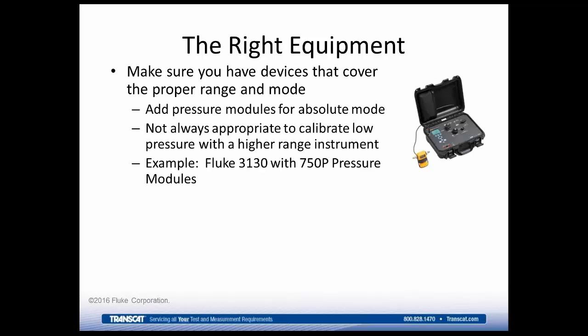And then finally, we need to make sure we have the right equipment. So make sure you have devices that cover the proper range and mode. If you've got a reference that's only a gauge mode device, but you routinely need to do absolute mode calibrations, then look at whether there are pressure modules or other such things, or maybe you need to get another device that can do absolute mode, so you can make sure that you're not inducing additional error that doesn't need to be there. It's also not always appropriate to calibrate low pressure with a higher range instrument. The errors and inaccuracies of the measuring device are oftentimes a function of its range. So if you've got a gauge that's 1,000 psi and you're trying to measure 1 psi with it, it may not work very well for you.